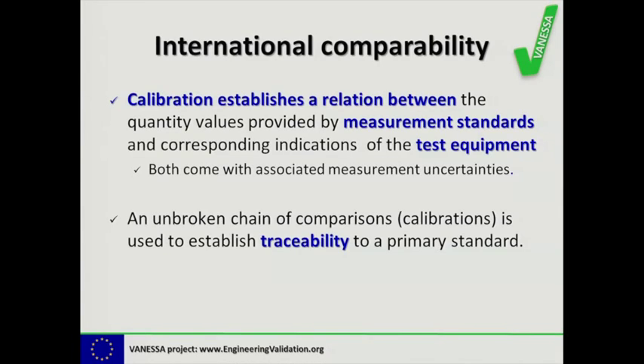The final point is international comparability. Calibration by definition establishes a relation between the quantity values provided by a measurement standard and the corresponding indications of your measurement or test equipment, both coming with their associated measurement uncertainty. This allows you to compare your results to an internationally recognized standard, and an unbroken chain of such calibrations establishes traceability to a primary internationally recognized standard.